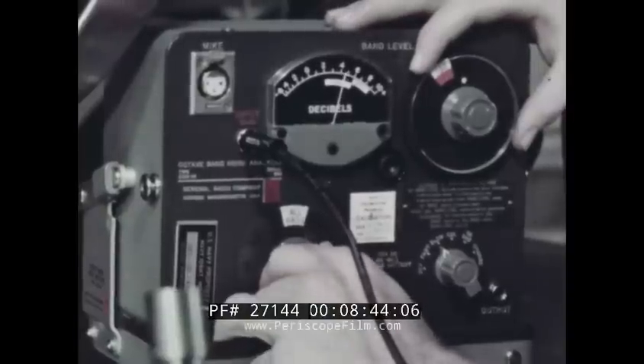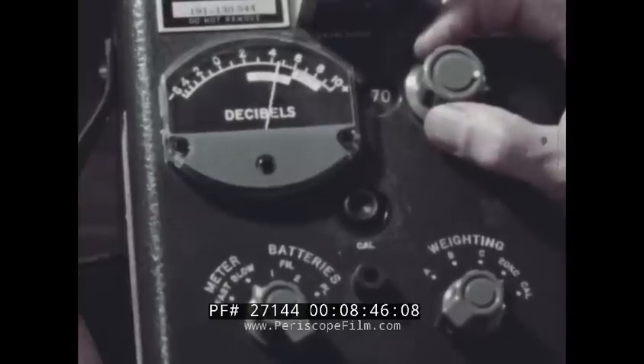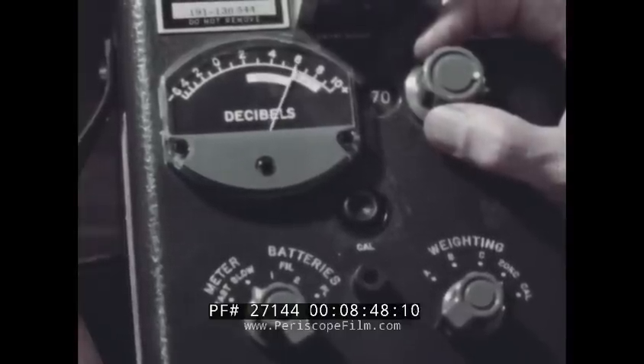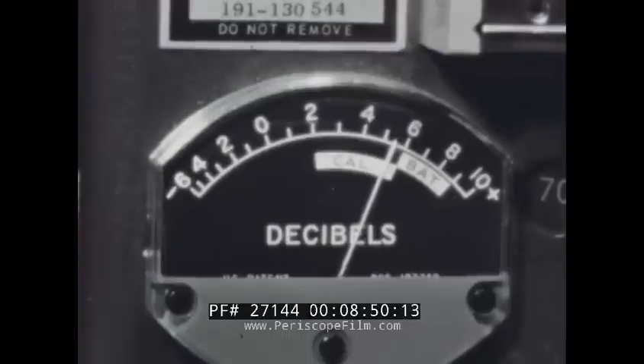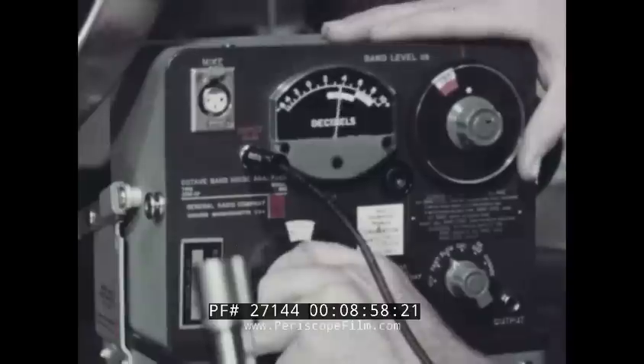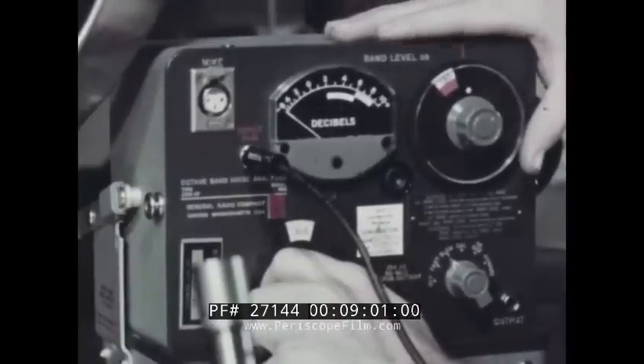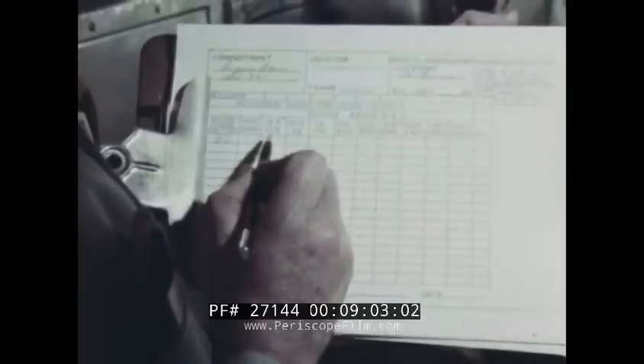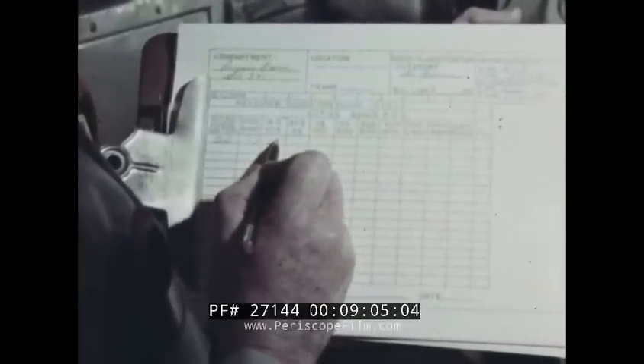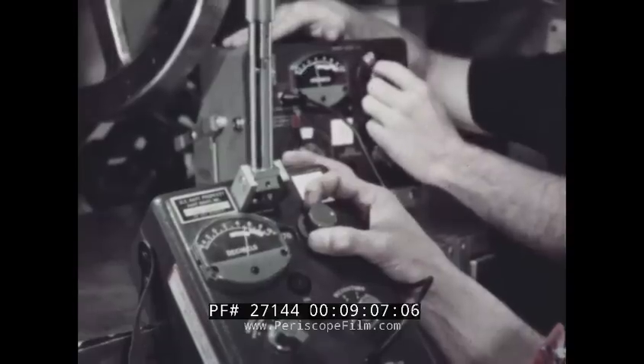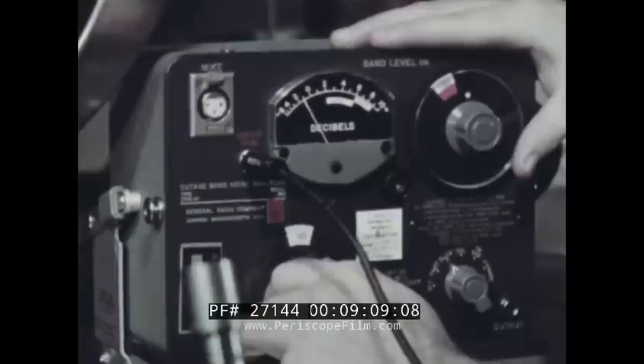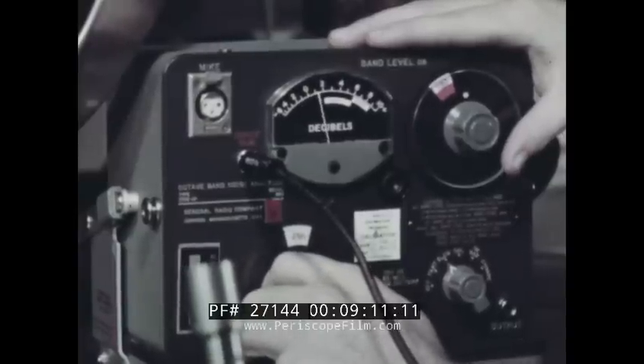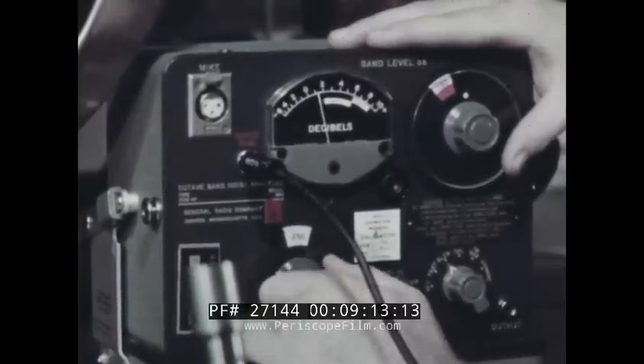The reading is always obtained as the sum of the attenuator setting plus the meter indication. In this case, 70 plus 5, or 75 dB. That's broadband, the total background noise level. A more detailed picture is provided by the analyzer. Take dB readings in the same manner for each frequency range.